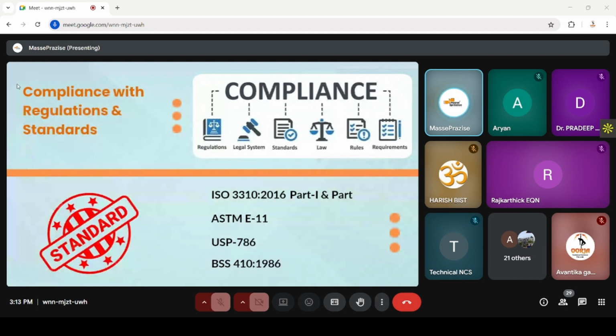Test sieve standards relate to the construction of the test sieve itself, as well as the performance of the sieves. There are two types of standard that are most commonly used. One is ISO 3310, the 2016 version, and the second is ASTM E11. Typically, ISO standards are international standards and ASTM is the North American standard. There are a few more standards, like British Standard BS 410, and some industry standards like USP 786, US Pharmacopeia 786, which is specifically for the pharmaceutical industry. Some other industries, like mining and agriculture, may have their own standards. So it is very important to identify your requirement of the standard and to follow it.